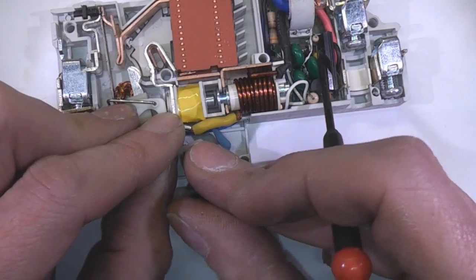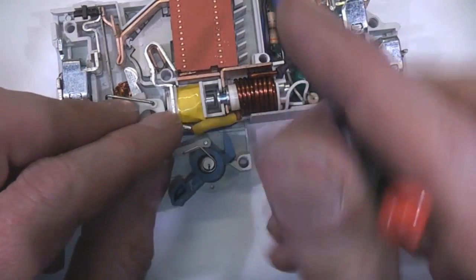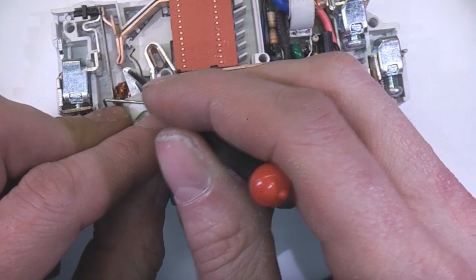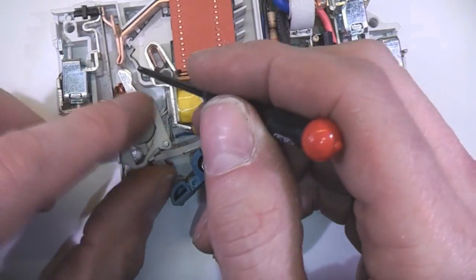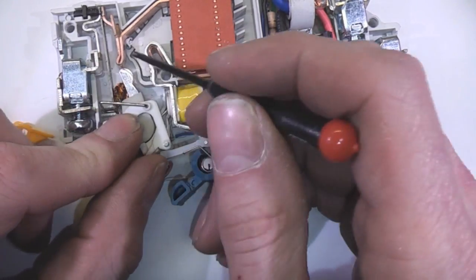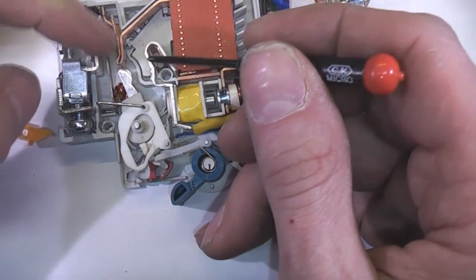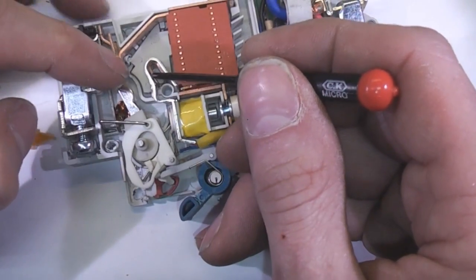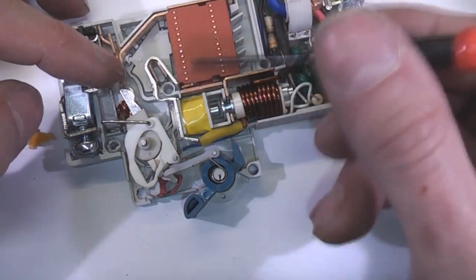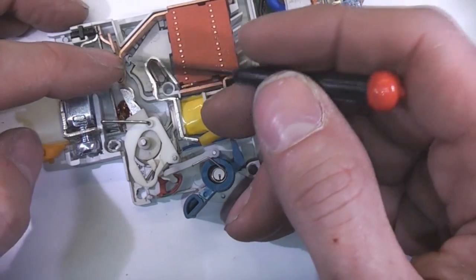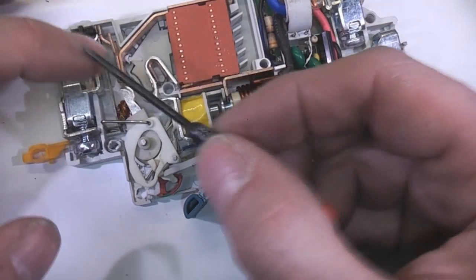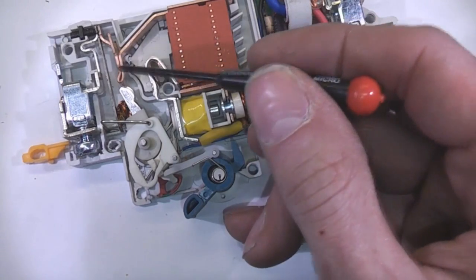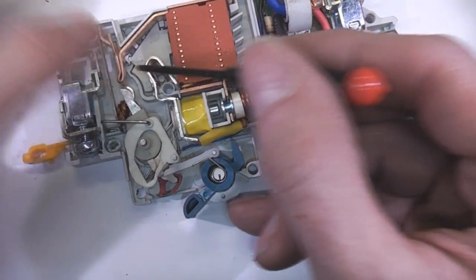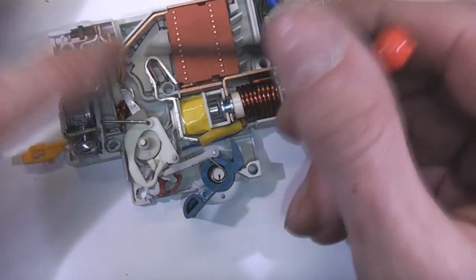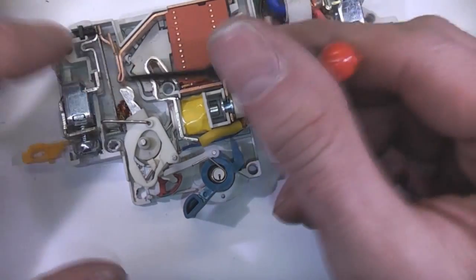And so as this carries on open, again in the worst case scenario, the arc is still continuing by the time it opens, and the geometry of this is designed so that the arc actually transfers to this strip. So we've now got this arc across here. Again, at some point this arc will extinguish. There's a big difference between AC and DC breakers, and the thing about the AC, because the current goes to zero every half cycle, that will generally tend to extinguish the arc, although you can get some residual gas sort of floating around. It will typically extinguish, if not on the first half cycle, within the next one or two.